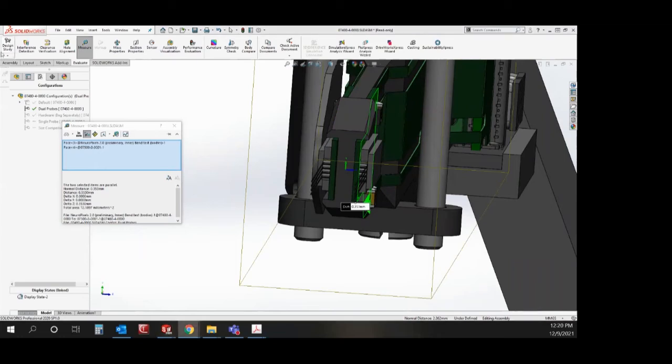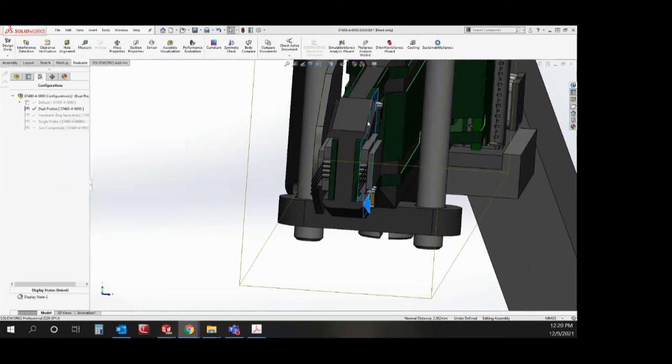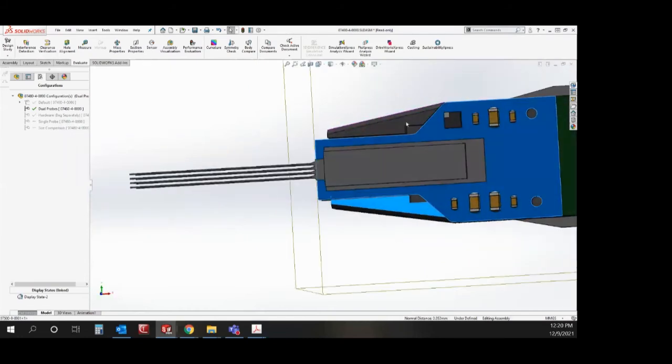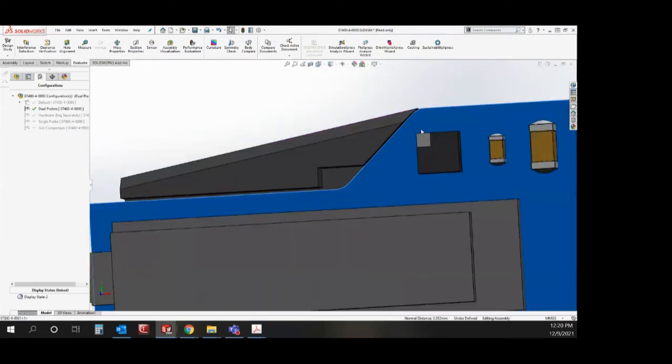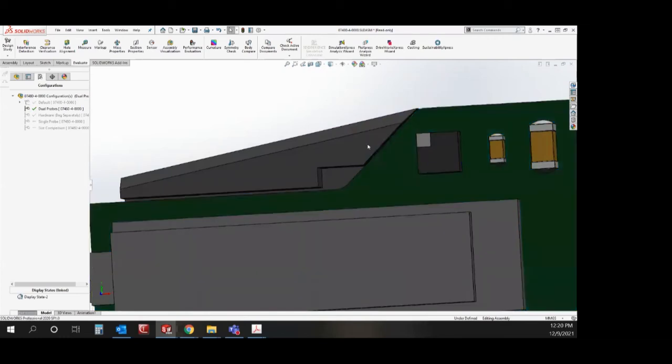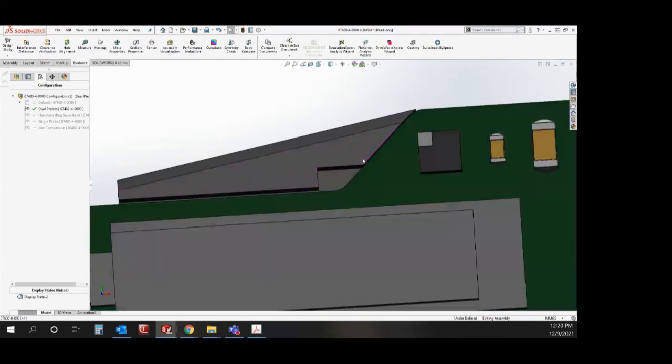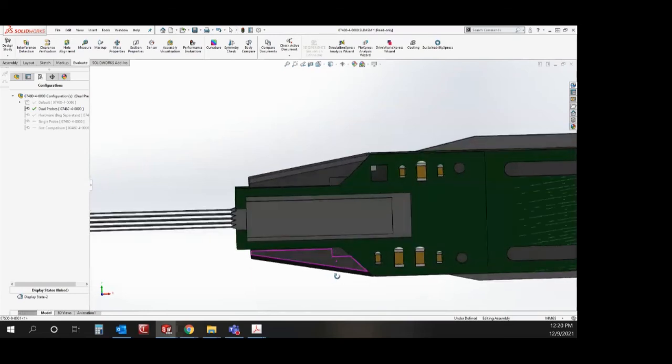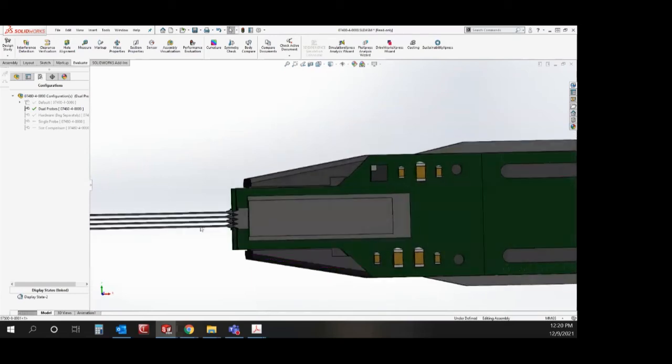As for installing the probes, thanks again for your questions. I do recommend first at least trying to place the probe PCB right up against these angles and checking the alignment with our alignment fixture. And if needed, if the probe shanks are not aligned well to the probe PCB's features, then back it off just a little bit and adjust accordingly. But for the initial installation, I would recommend putting it right up against these angles.